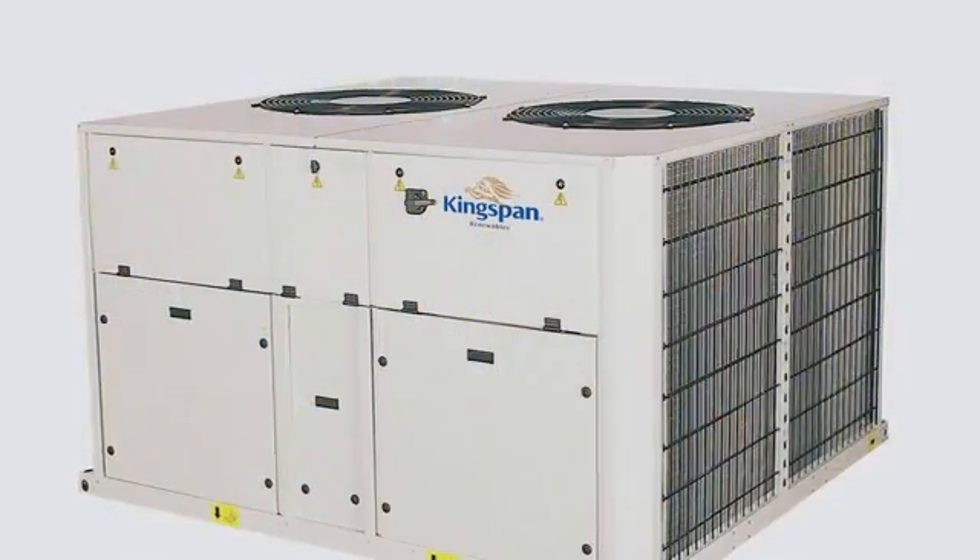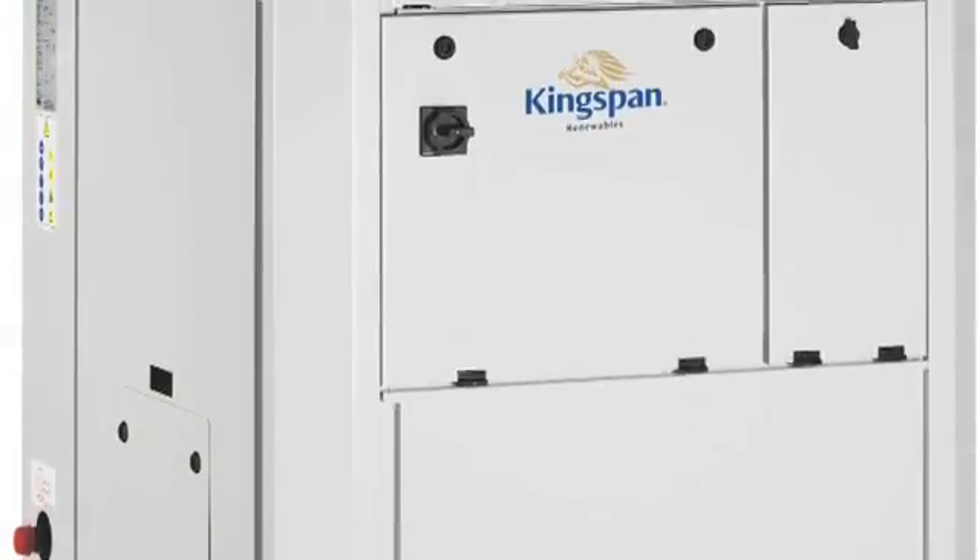The Air Max Plus commercial air source equipment unit is specifically aimed at the commercial industrial end of the market, supplying commercial renewable installers, M&E contractors, and targeting M&E consultants. The key benefits of the commercial air source units is the heat ranging from 22 kilowatts to 105 kilowatts, where we can link two units together to give a total heat output capacity of 210 kilowatts. With a scroll compressor unit using an economiser vapour injection system, we can reach high temperatures of 65 degrees C and still maintain a high COP level.